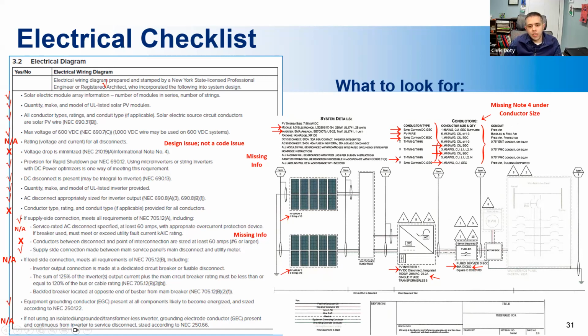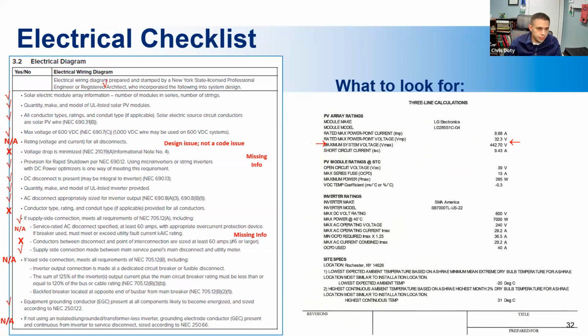And doing this makes it easier for the reviewer to not miss details. These are typically very detailed systems. You want to make sure that you get all the details correct, so as to avoid having a system installed that is dangerous. And you want to go through all this prior to issuing the permit. So just more examples of what you're looking for, and how you draw the correlation between the electrical diagram and the information, and then the checklist. And you want to make sure that all the calculations are done correctly and there's no missing piece of information that would be necessary to evaluate the system.